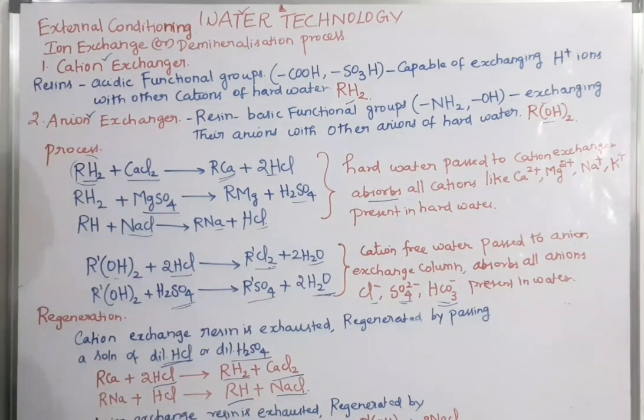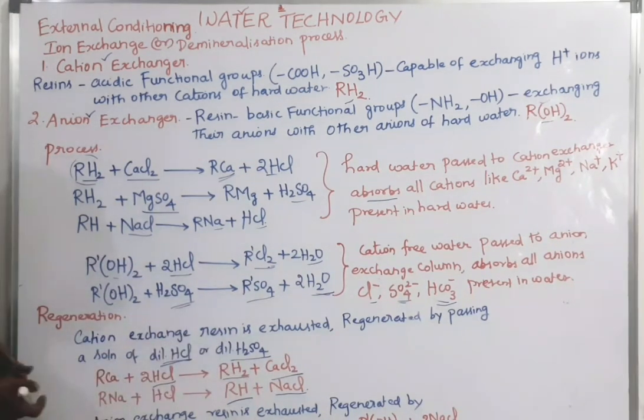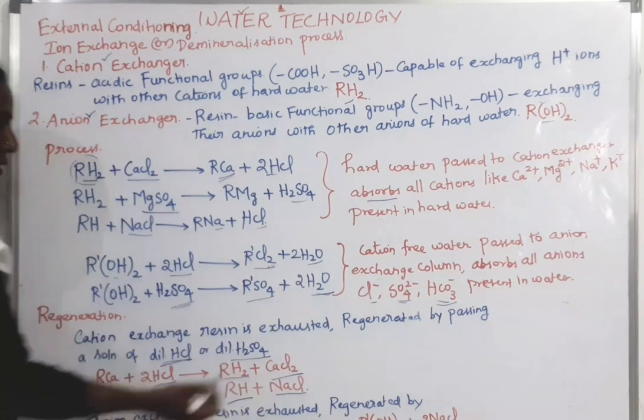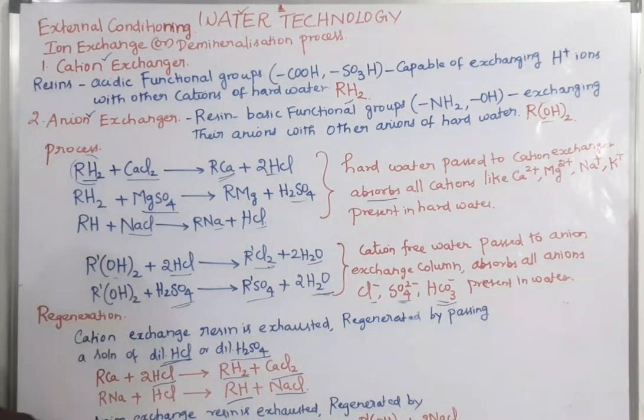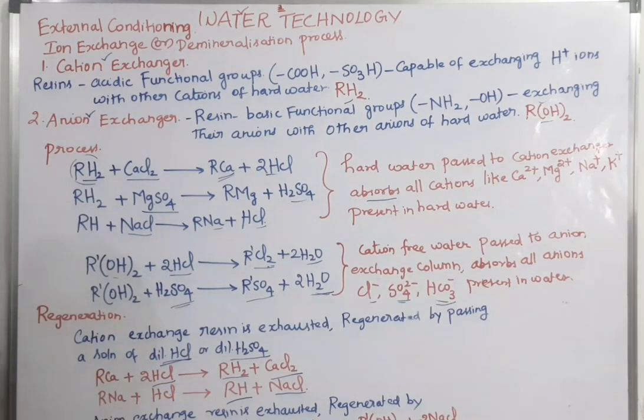Next we will see about the regeneration. When the cation exchanger is exhausted, it is regenerated by passing dilute HCl or dilute sulphuric acid. Similarly, when the anion exchanger resin is exhausted, it is regenerated by passing dilute sodium hydroxide.